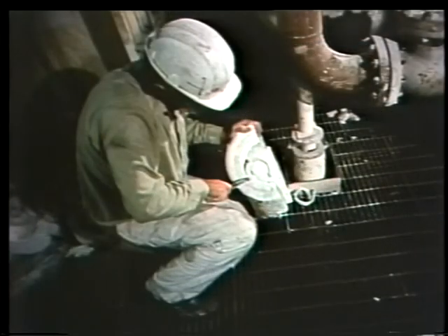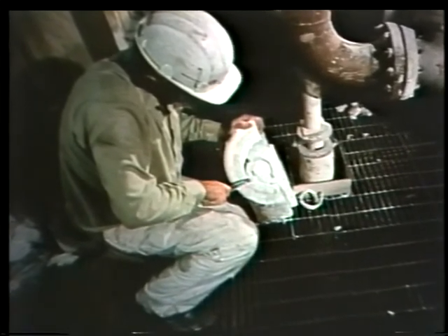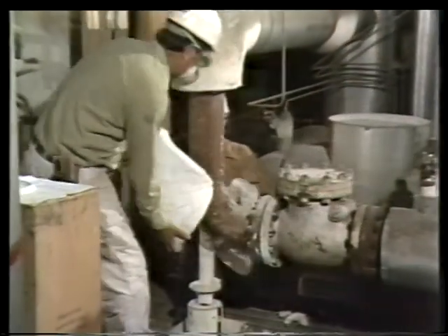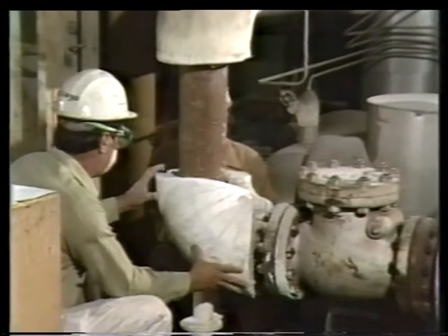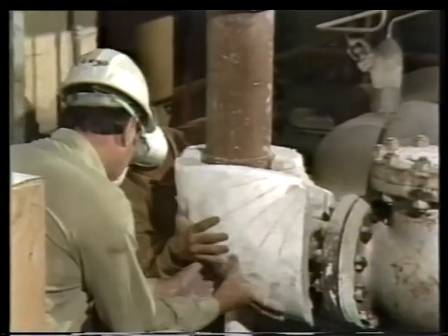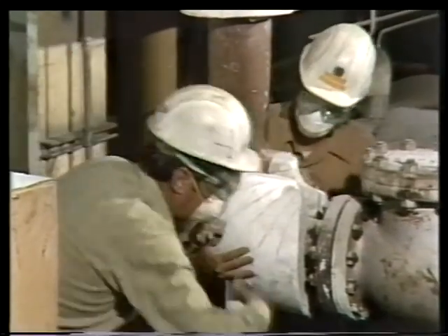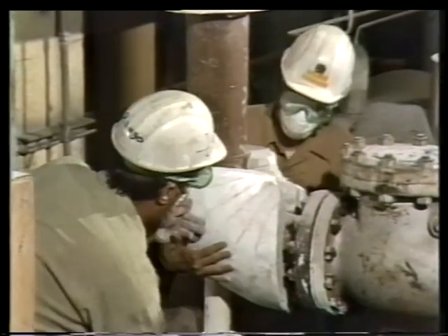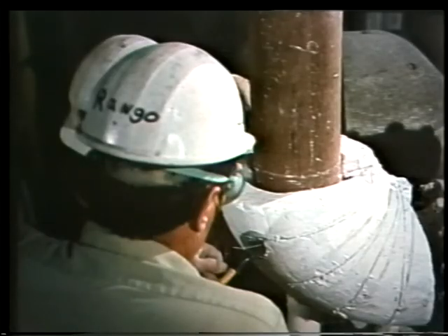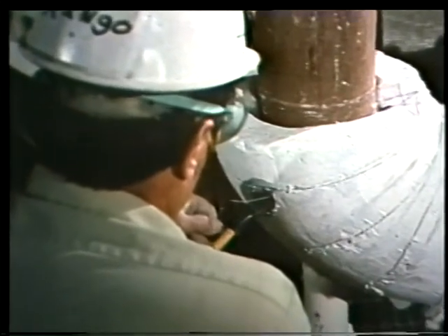Before the insulation can be replaced, the new elbow insulation must be carefully trimmed to fit around the riser and the weld bead. Then, both halves are fitted over the elbow. If they've been trimmed correctly, the insulation fits close to the pipe all the way around, and both halves mate together with no gaps. The halves are wired together loosely. Then the wires are tightened and sunk flush with the surface.